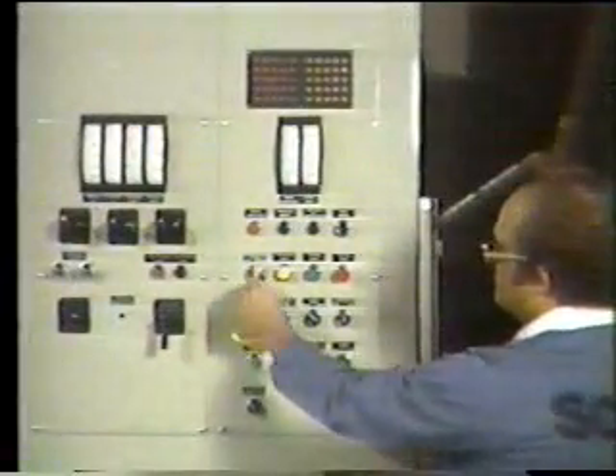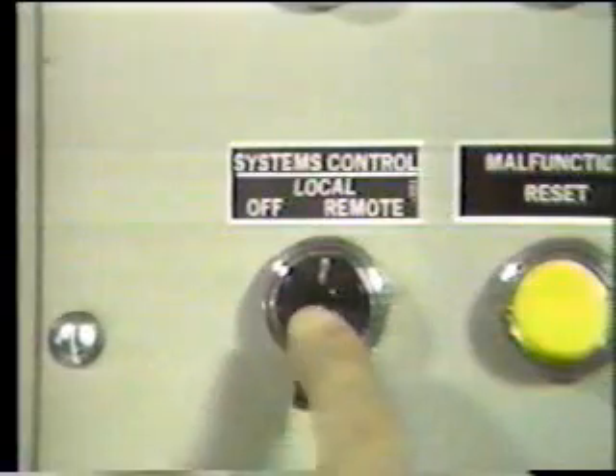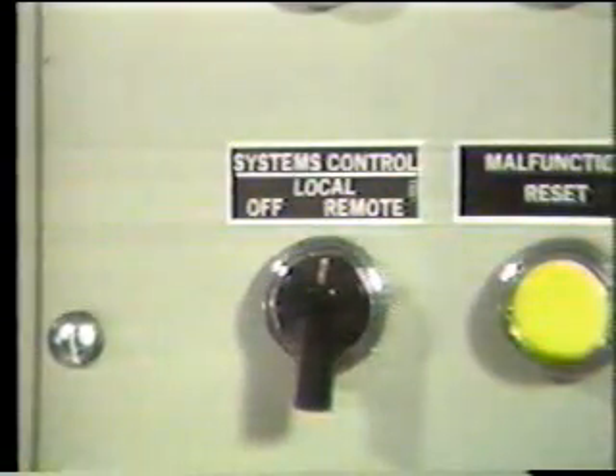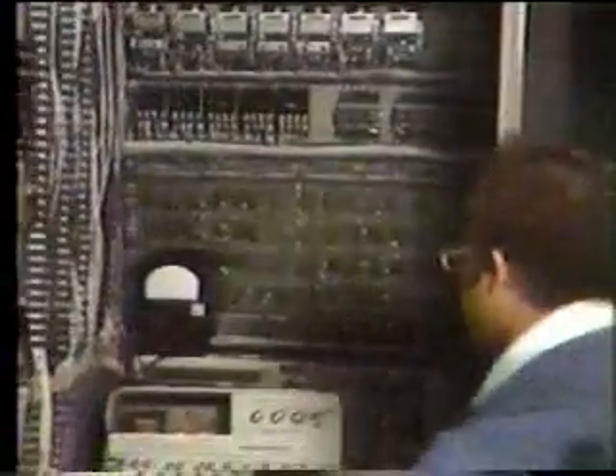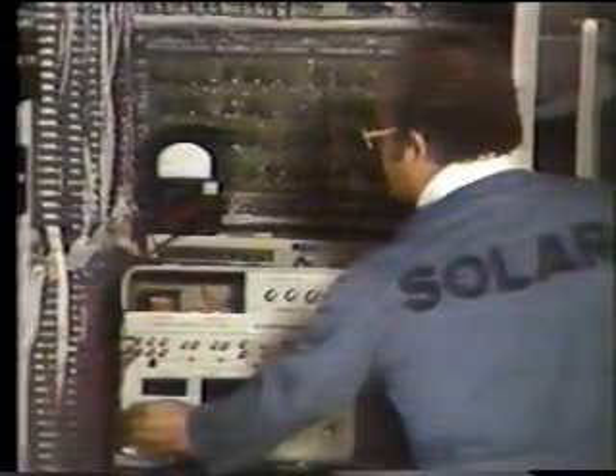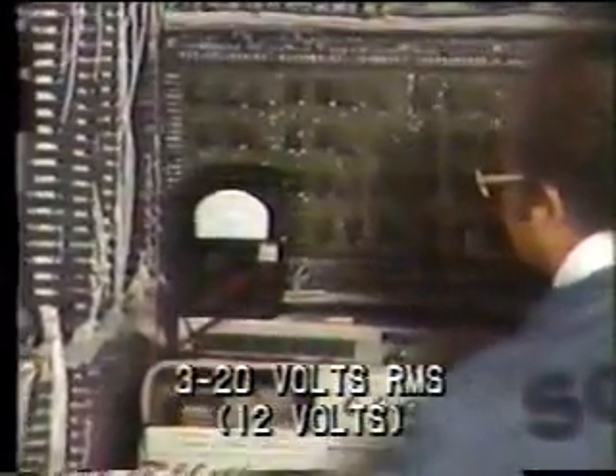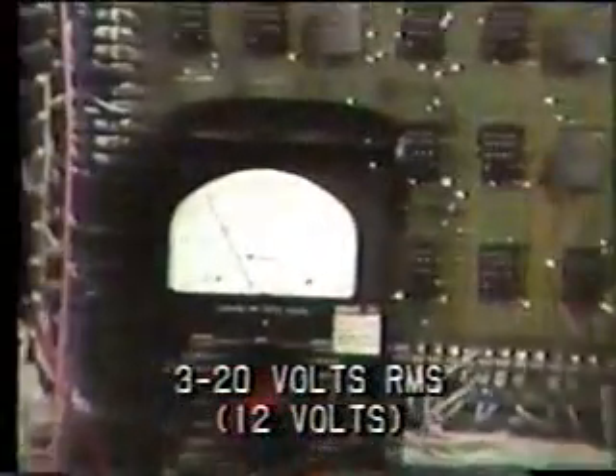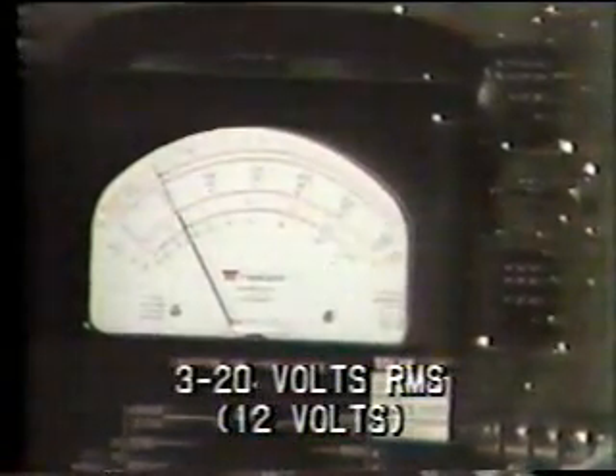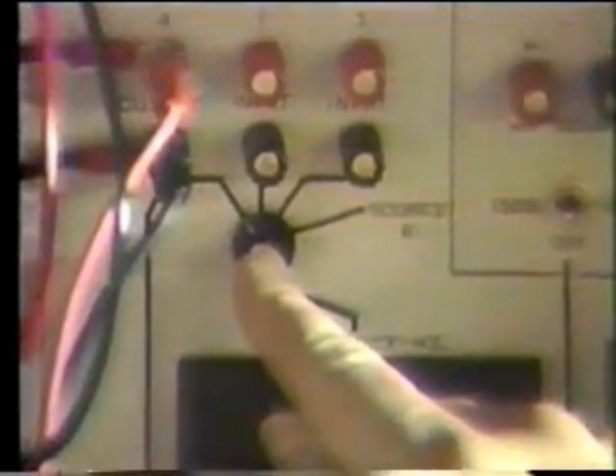Now, turn on the control console power. Then place the master switch S01 to local. Now, turn on and adjust the output of the signal generator to between 3 and 20 volts RMS. During our test, we'll set the output at 12 volts RMS. The output can be measured with the voltmeter. Note that when we turn on the signal generator, the built-in digital counter illuminates its display of the output frequency. Be sure that the selector switch is on source A.